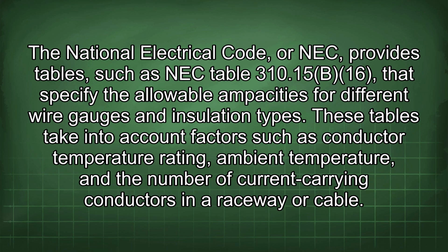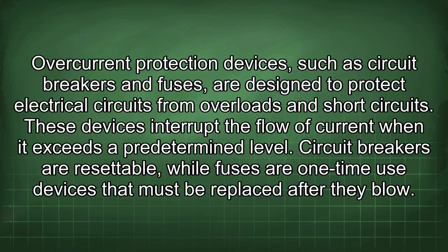a raceway or cable. Overcurrent protection devices, such as circuit breakers and fuses, are designed to protect electrical circuits from overloads and short circuits. These devices interrupt the flow of current when it exceeds a predetermined level. Circuit breakers are resettable, while fuses are one-time use devices that must be replaced after they blow.